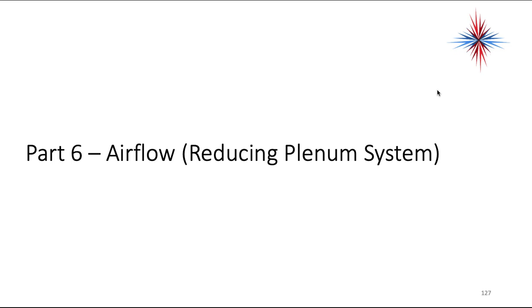If you remember from the last video — that's part 5 — we talked about the extended plenum system. The extended plenum system had the same size ductwork, the same square footage, basically the same area of ductwork, all the way down the system. And we lost velocity near the end of the system.